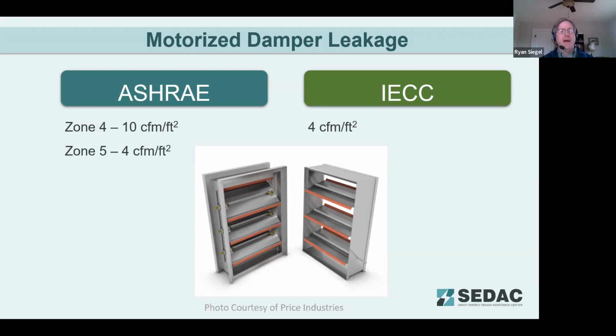So motorized damper leakage. This is another one where IECC just has one standard that covers both climate zones 4 and 5 here in the state of Illinois. ASHRAE kind of has a little split in here. So the warmer south portion of the state of Illinois can allow leakage of up to 10 cubic feet a minute per square foot of area during the standard test procedures. Whereas if you're in the colder climate zone 5 towards the northern part of Illinois, that's going to be 4 CFM per square foot.